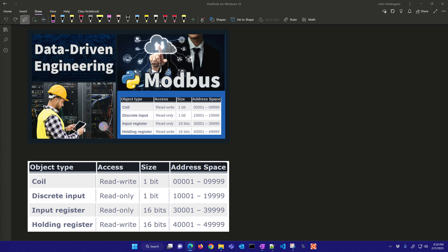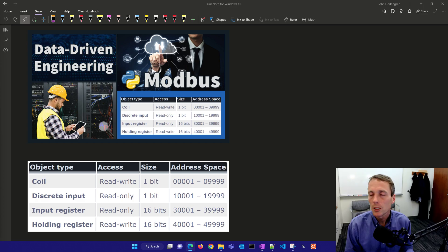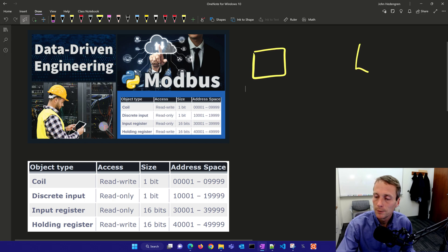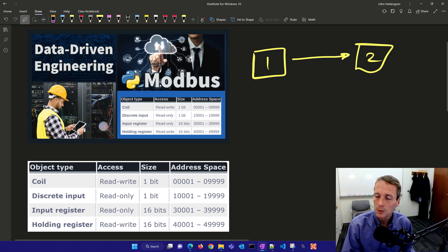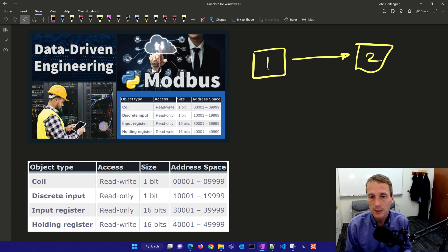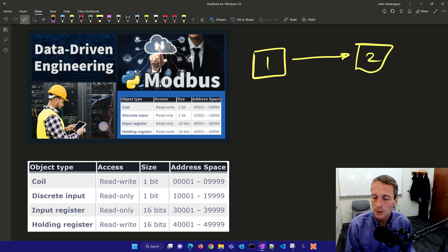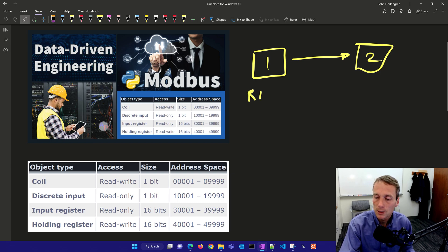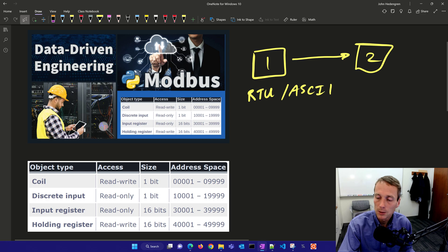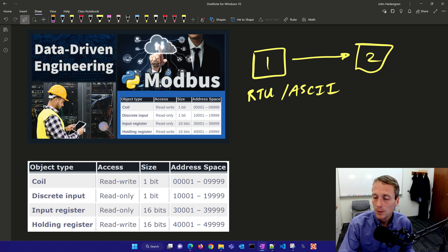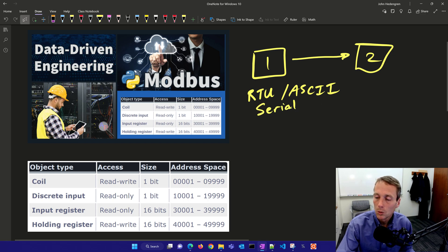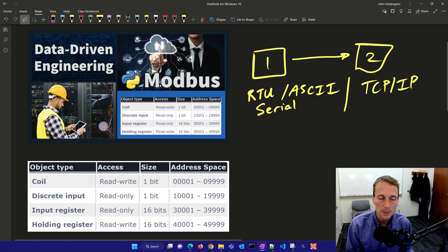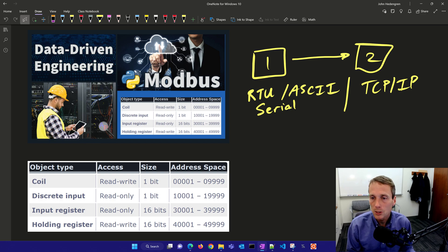Modbus is a communication standard to transfer values between computers. Let's say I have computer one and computer two and I want to transfer values over to the other one. It's a very simple networking communication protocol designed back in the 1970s. Its simplicity and basic nature means you could transfer very fast over a serial connection, either RTU or ASCII mode that takes about twice as many characters. These are through serial connection or you can transfer through an Ethernet connection, so TCP/IP. You have either serial or TCP/IP for communication.